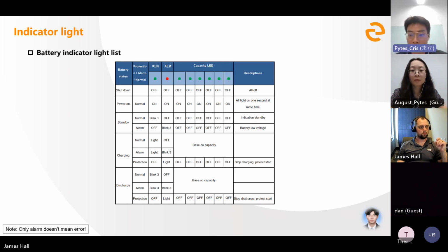When the battery is on standby, if normal, only the run light will flash every second with the other lights all off. If alarm, the alarm light will flash every 3 seconds with the other lights all off. Alarm may be caused by high voltage, high current, high temperature, and so on, which is a reminder before entering the protection state.